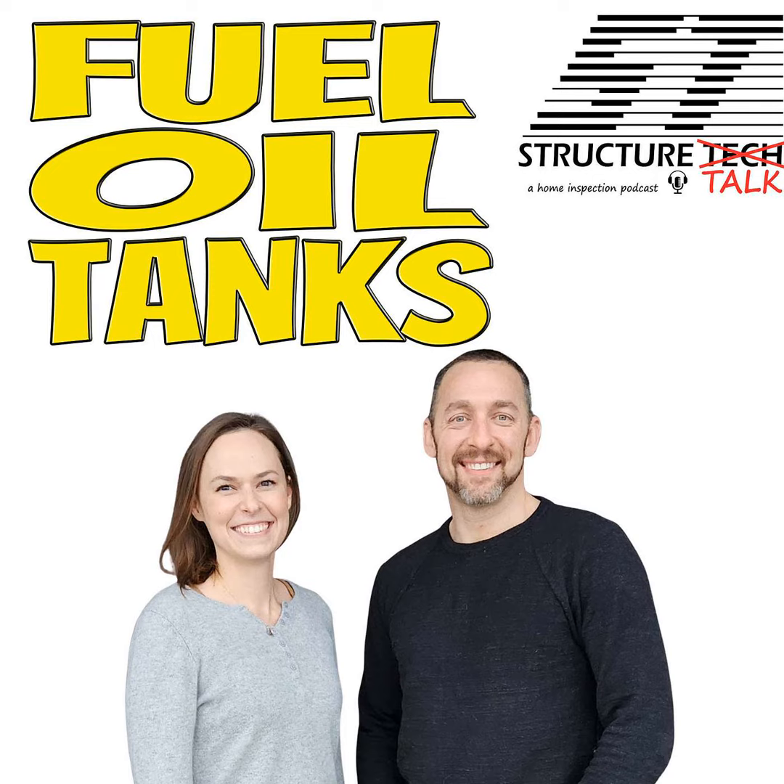Why does it matter if you've got an abandoned tank besides the fire code? Most of these tanks have been out of service for at least 40 years. They're basically just a buried steel container with no coating, no galvanization — just bare steel. Elements are going to take their toll, whether it's water or salt if they're under garages. A car sitting in air rusts out quickly — imagine a bare buried steel container with no protection at all. They just rot out, and right now about 85 to 90% of all buried tanks are leaking.